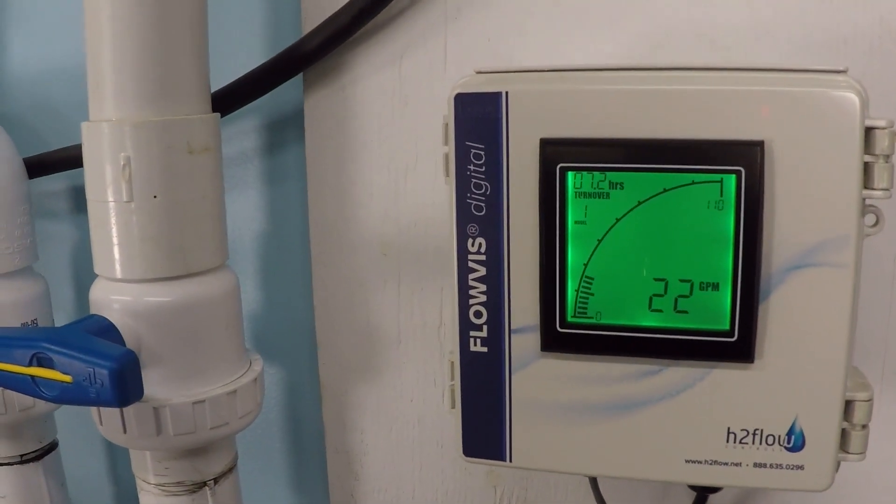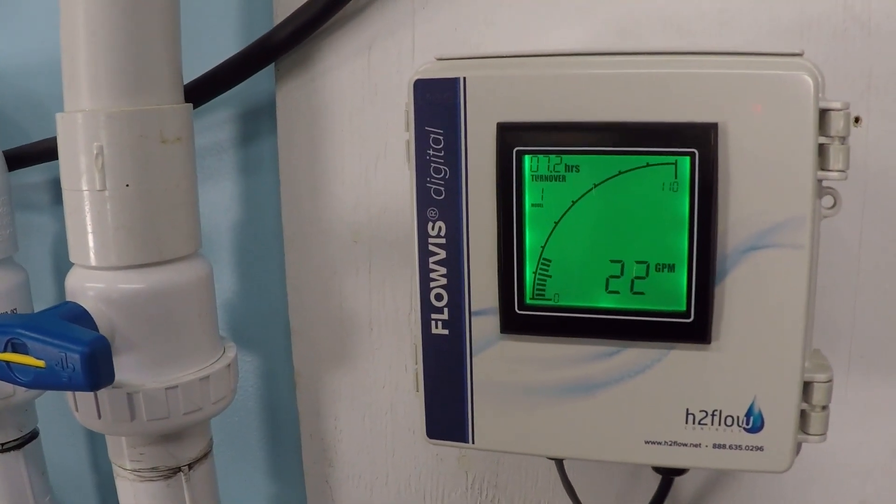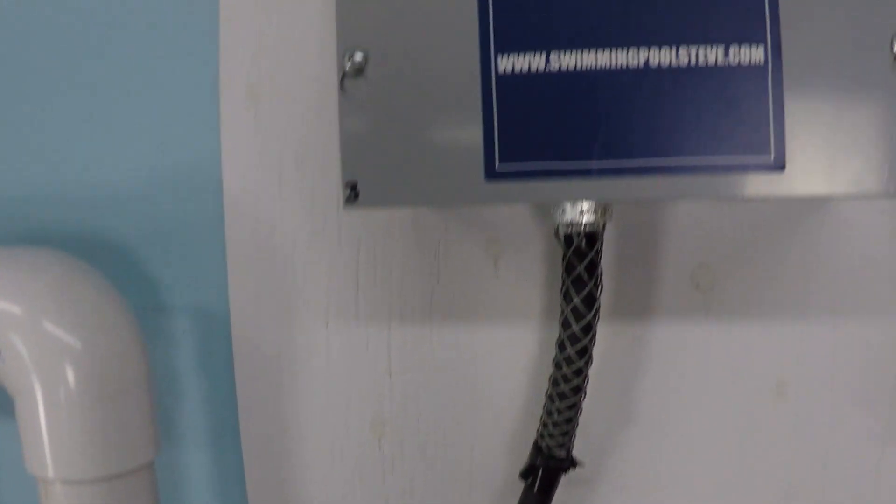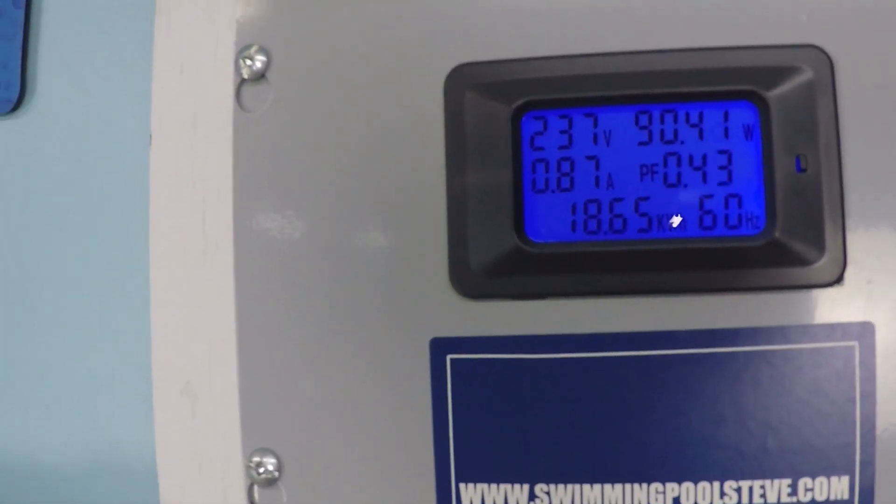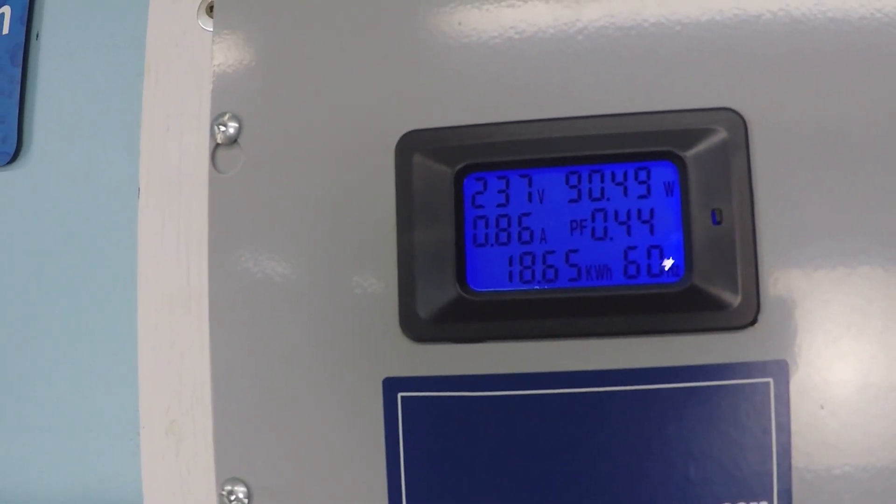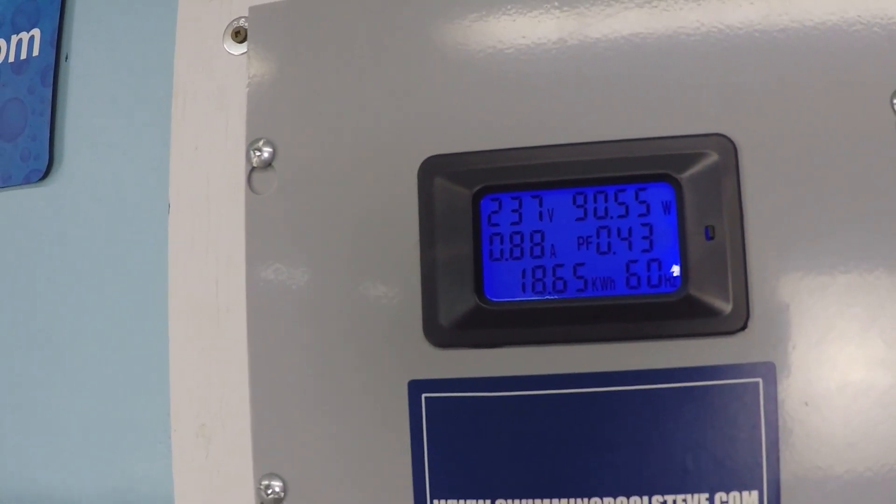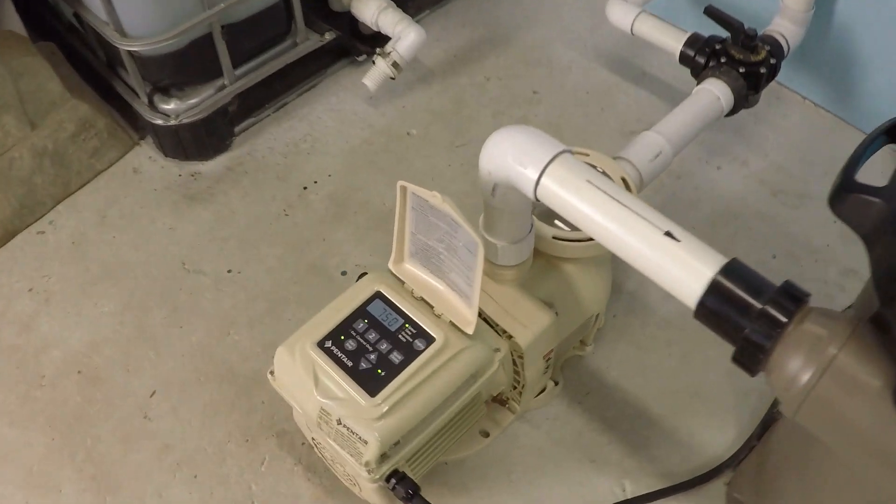Right now we're already running at 750 RPM so that's going to be our first test point and as you can see we're achieving 22 gallons per minute. At the top right corner, just over 90 watts is what the pump is consuming at 750 RPM.